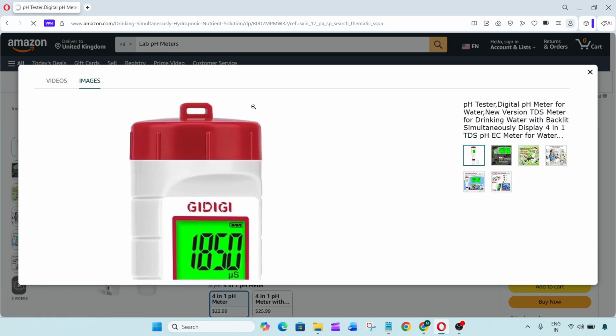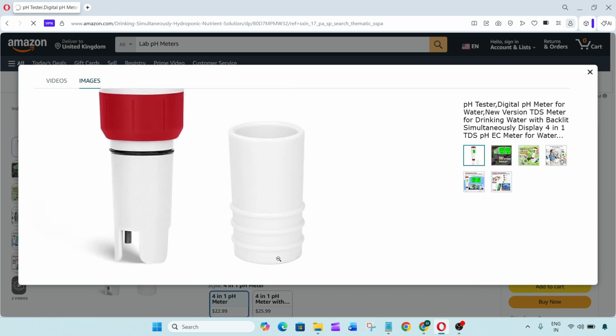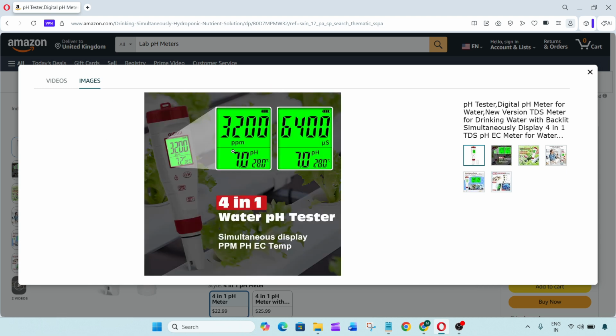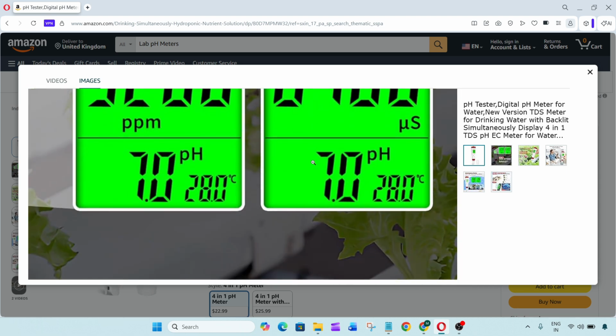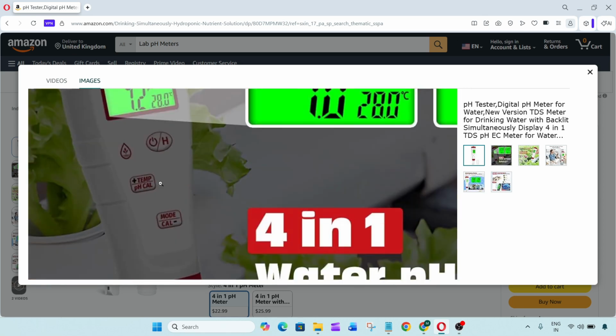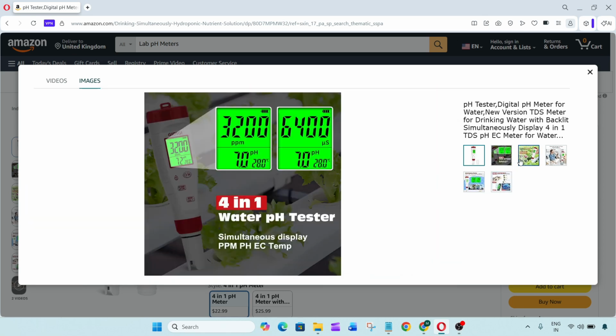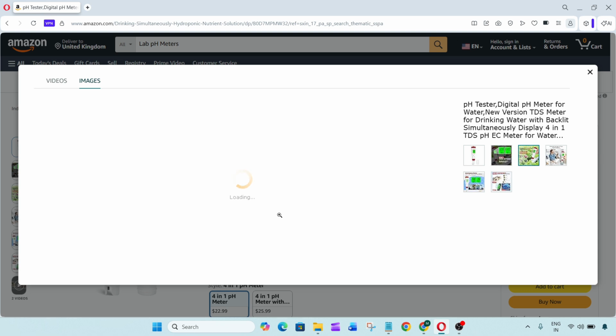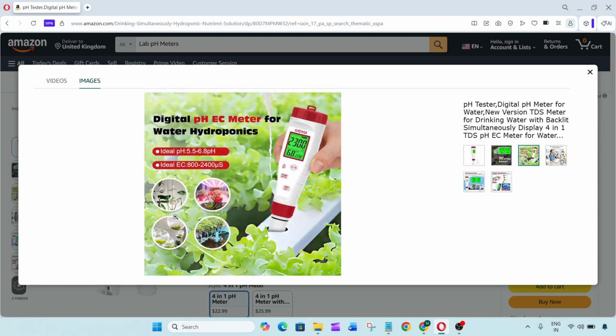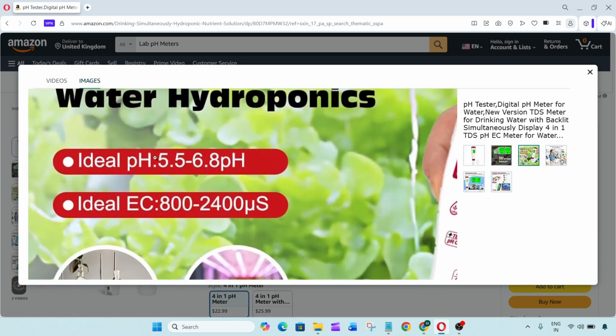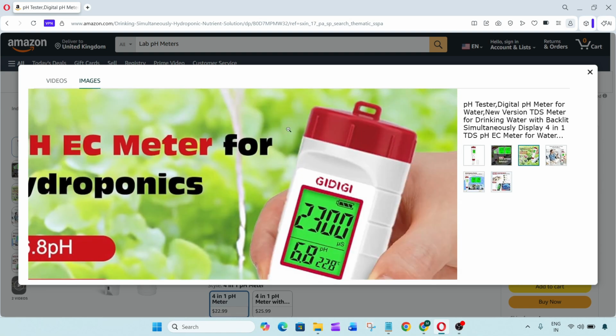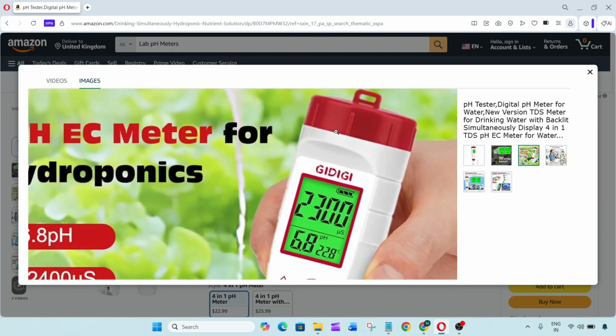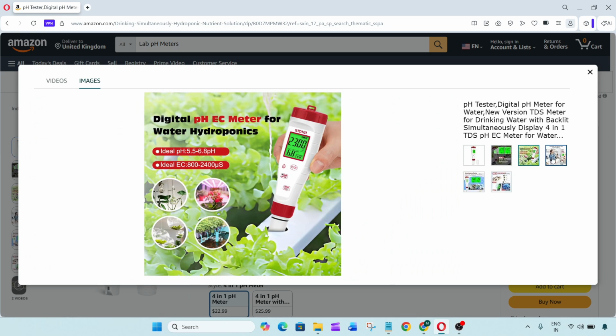A pH meter is designed to provide precise measurements, but over time you may notice readings that seem inconsistent, unstable, or completely different from what you expect. In many situations, the issue is not a major failure, but rather something related to calibration, probe condition, storage practices, or sample preparation. Even a high quality pH meter can produce inaccurate results if one of these areas is overlooked.